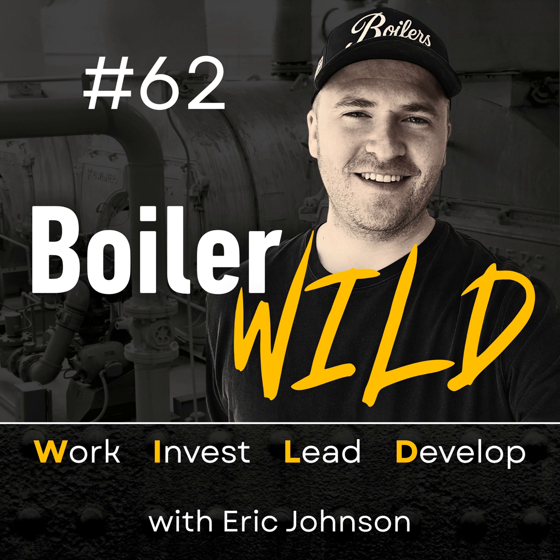And then, last point, avoid the parts cannon. If you are loading the parts cannon and just blindly changing parts without actually diagnosing why a part is bad or how it's partly failed, you are just guessing. Guessing is not troubleshooting, and guessing is for hacks. Listeners of the Boiler Wild podcast are not hacks. You are to troubleshoot the boiler properly, and you are to lead your customer in the correct way that they say, wow, I really hired a boiler expert. They know what they're doing.